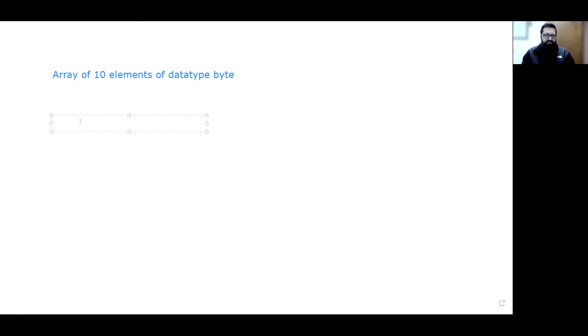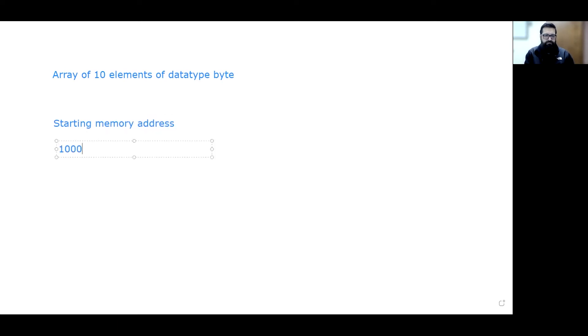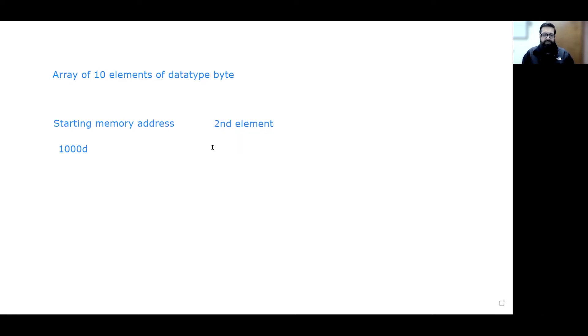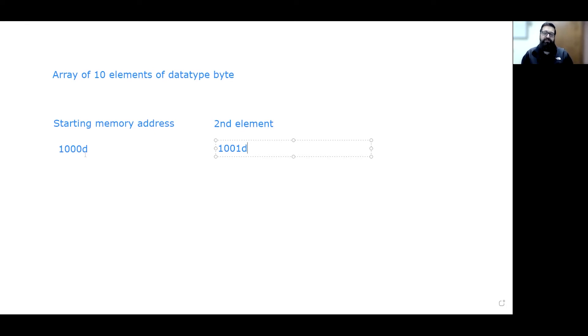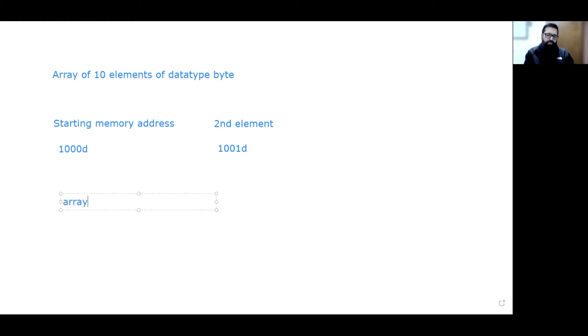If I were to create this in a PLC with a starting memory address of 1,000, I know that because the data type is a byte, the first element will be stored at address 1,000 and the second element will start at 1,001. So when I tell the PLC to access the first element of my array, it goes to memory address 1,000, grabs that value, and returns it. And if I grab the second element, it goes to 1,001 and brings that value back.